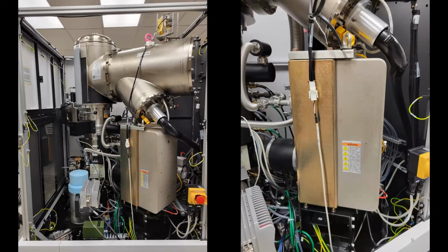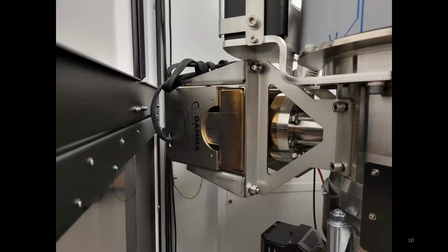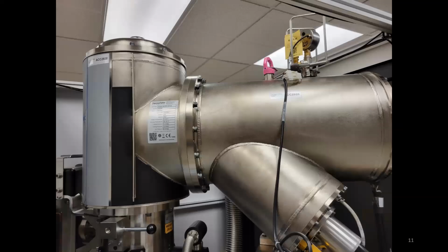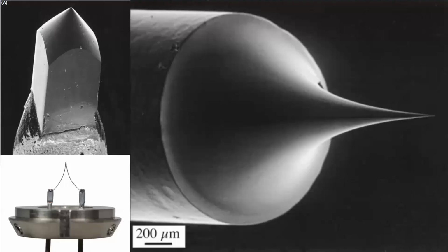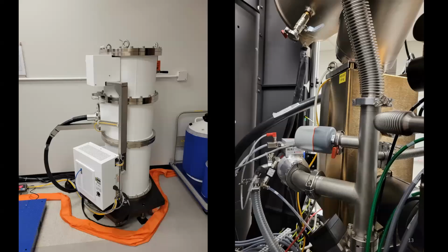So we have here a giant, this is the column vacuum pump. It's an ion gettering pump. Let's see. This little guy is for the gun, so also an ion gettering pump for the gun. We go to like 10 to the -9 torr on the gun, 10 to the -7 to -8 torr on the column, which is pretty high vacuum because we have a FEG, and we'll talk about that in a minute. And then, that jumped in there. We'll have to come back to him.